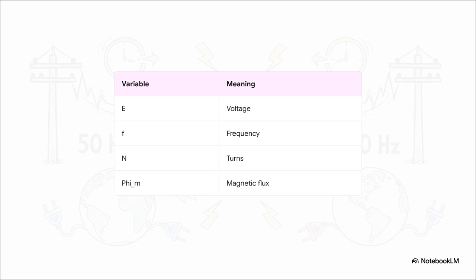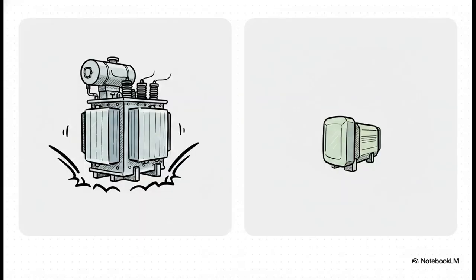This dictates the design of a power transformer. E is your voltage, F is frequency, N is the number of wire turns, and phi m is the maximum magnetic flux. I want you to think of frequency like a lever. When you pull that frequency lever up, let's say from 50 to 60 hertz, the need for maximum magnetic flux to achieve the exact same voltage actually goes down.